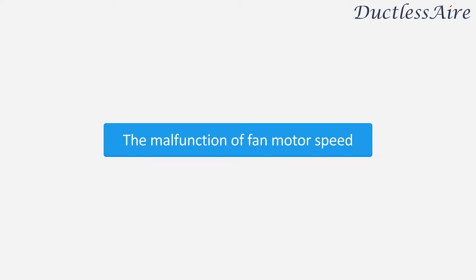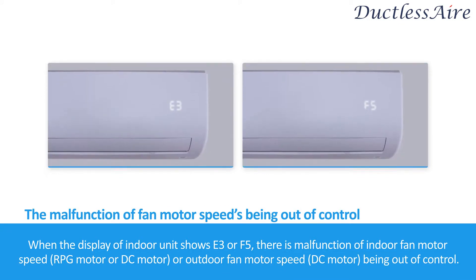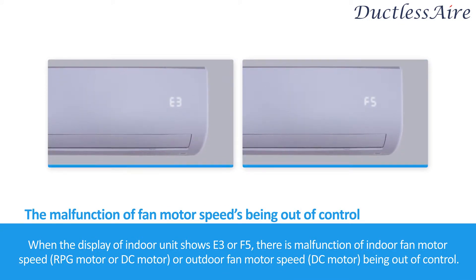The malfunction of fan motor speed. When the display of the indoor unit shows E3 or F5, there is a malfunction of indoor fan motor speed — RPG motor or DC motor — or outdoor fan motor speed, DC motor being out of control.